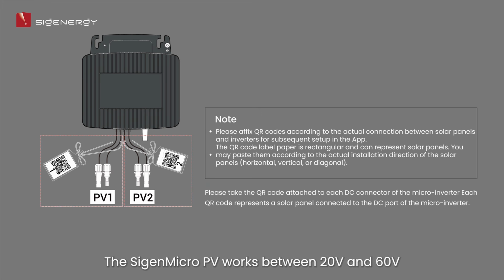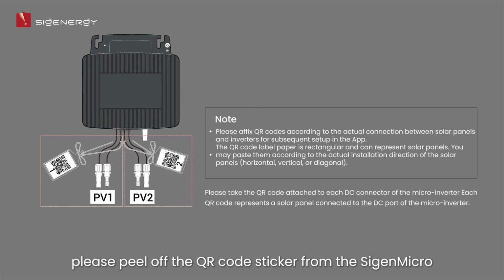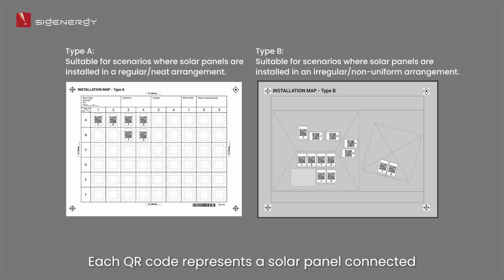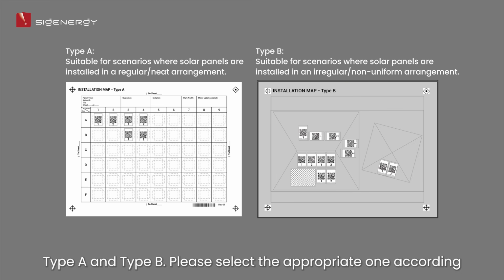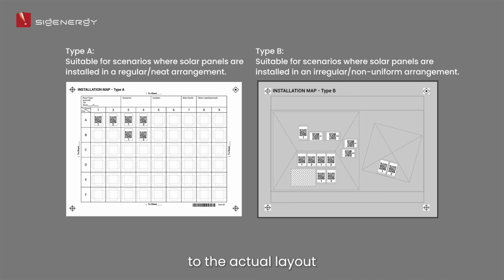The SigenMicro PV works between 20 volts and 60 volts. Any voltage higher than that will damage the unit. Before connecting the DC side, please peel off the QR code sticker from the SigenMicro. Each QR code represents a solar panel connected to the DC port of the microinverter. SiGenergy provides 2 types of installation maps, Type A and Type B. Please select the appropriate one according to the actual layout.